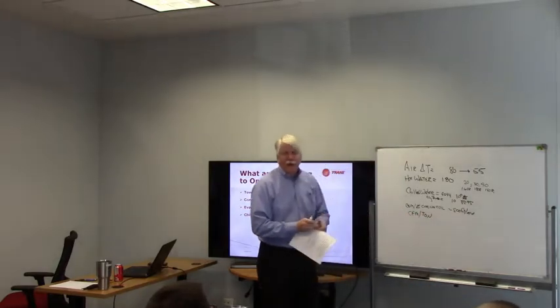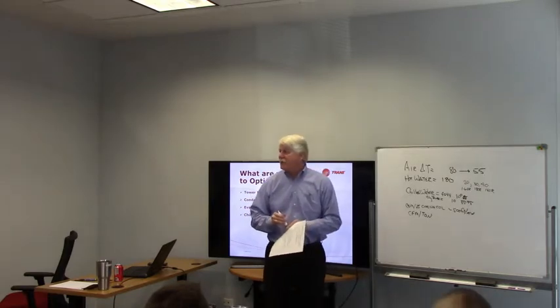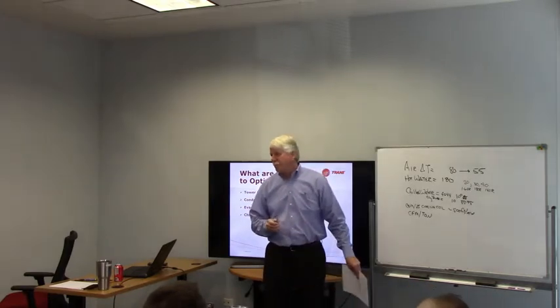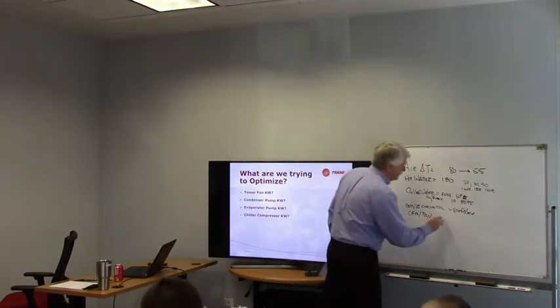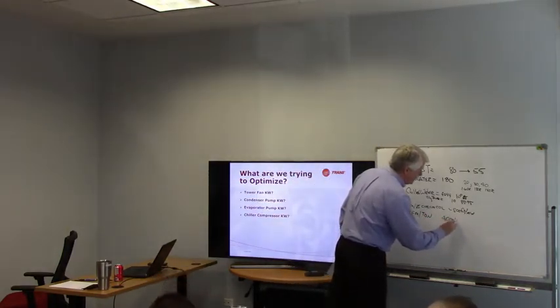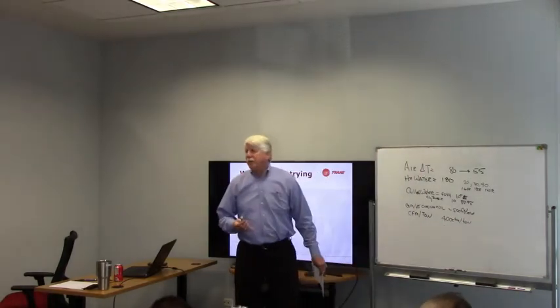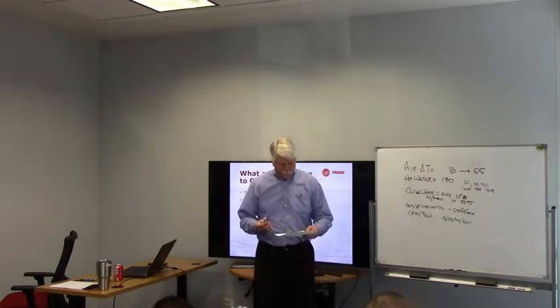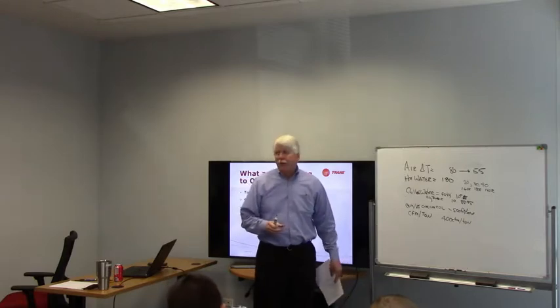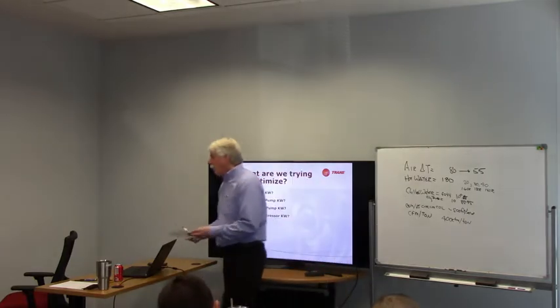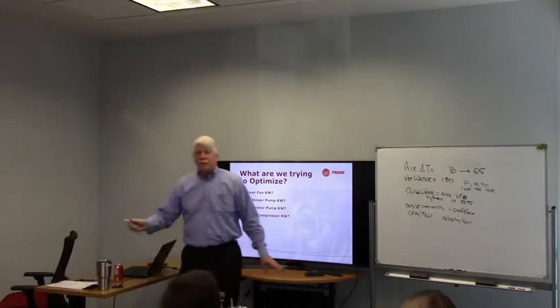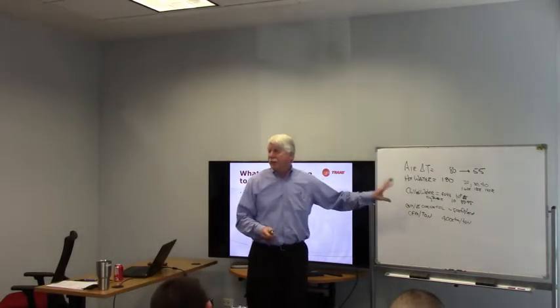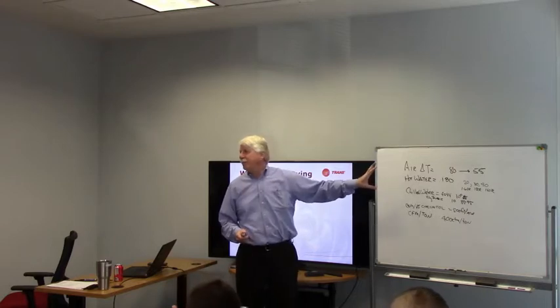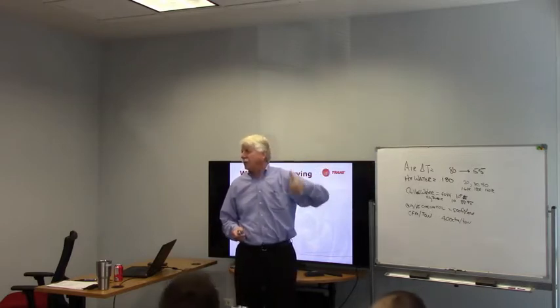Okay, so you've got an air handler and you figured out how many CFM it is, and now you want to know how many tons it is. Okay? Usually about 400 CFM a ton. Okay? Now the thing you need to know about all of these numbers is you can't absolutely apply all of these all the time. These are what are called rules of thumb, they'll get you close.